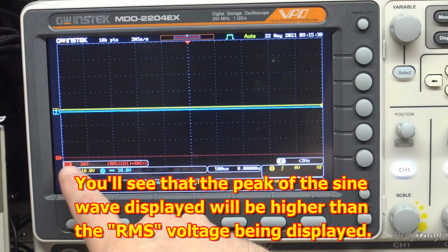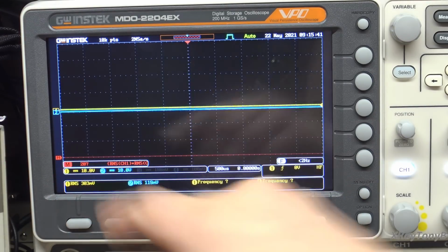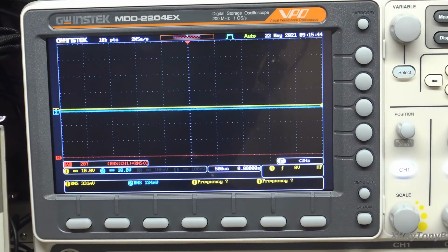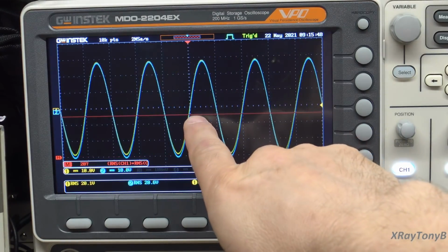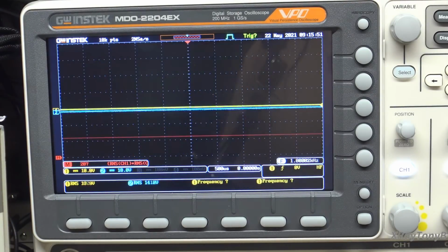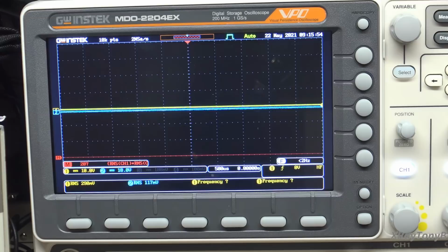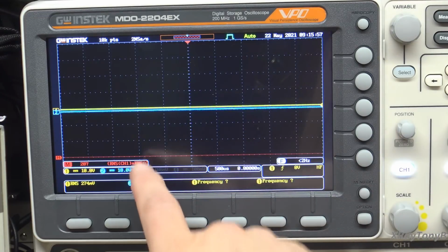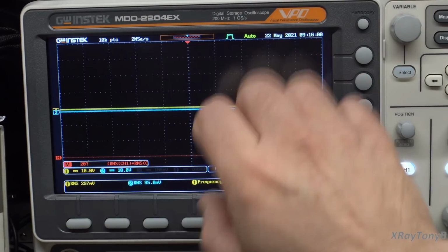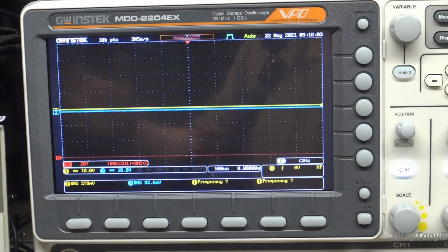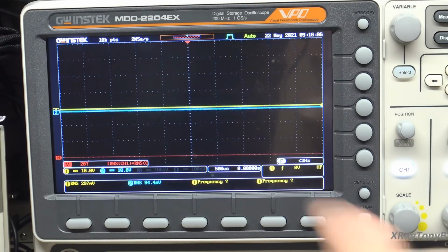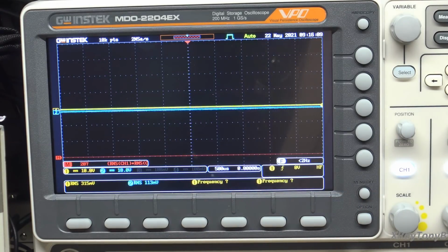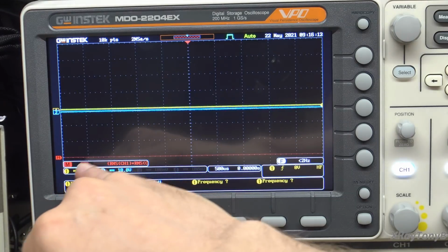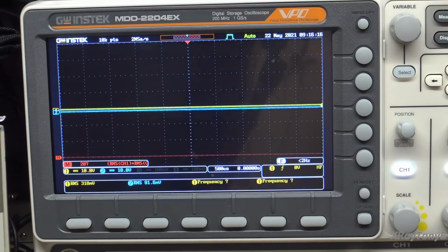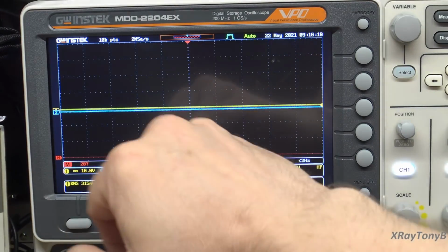So the first thing that I don't like is that you have to change this scale. One thing that I do like, as soon as I turn the signal on, bam, the measurement is instantaneous. Now, I don't know if you remember on some of my previous videos using the Tektronix TDS 3032, but you have to have that signal on for a while before the math will actually display. It takes a lot more averages and it takes a lot longer to calculate. This one calculates very rapidly. The downside is it does that because it does not auto scale. The Tektronix will actually auto scale, so it takes a little longer to display the output.